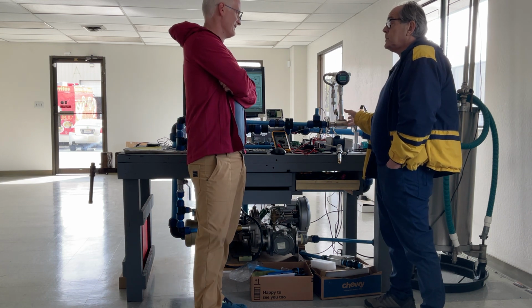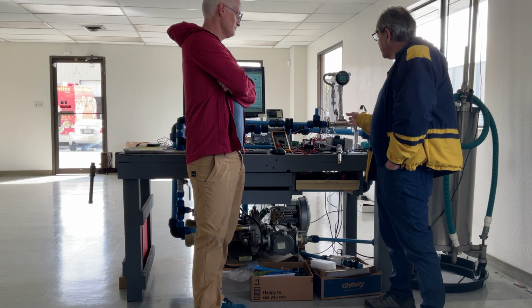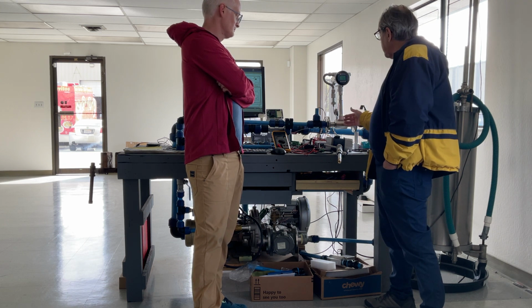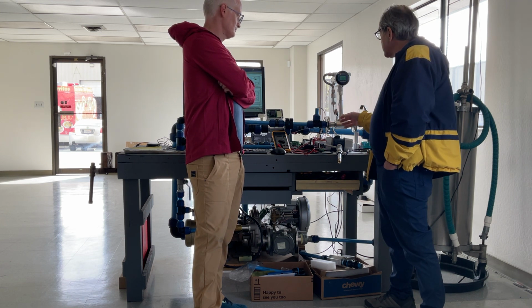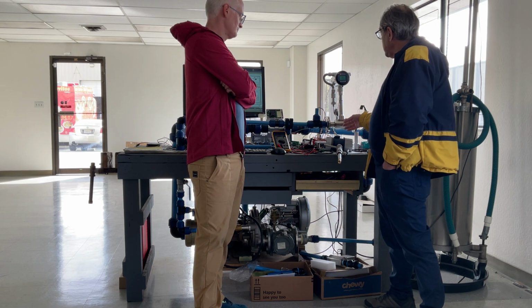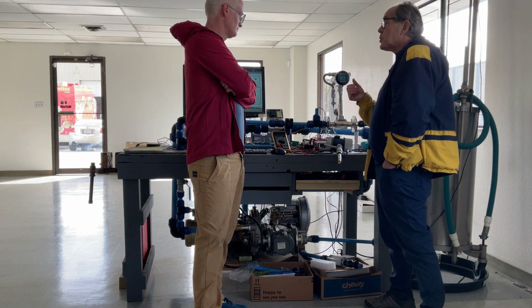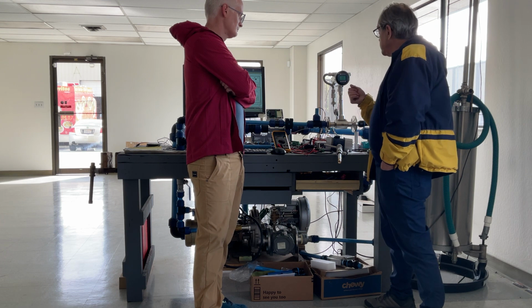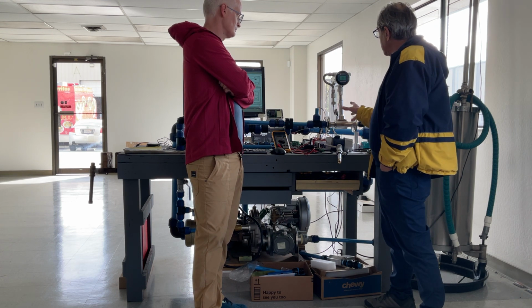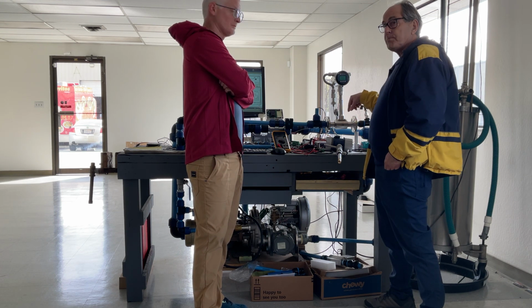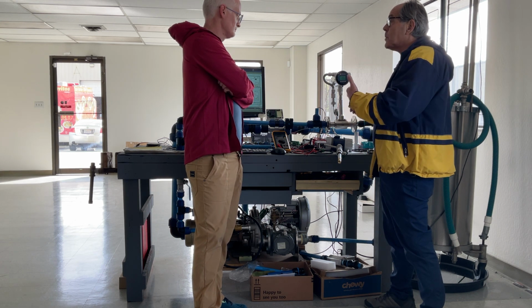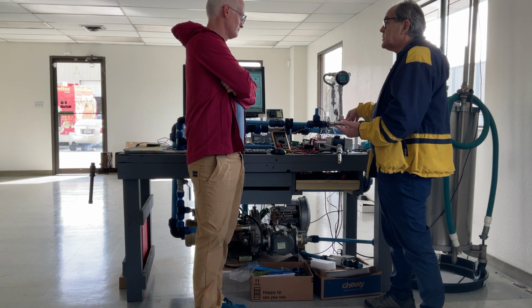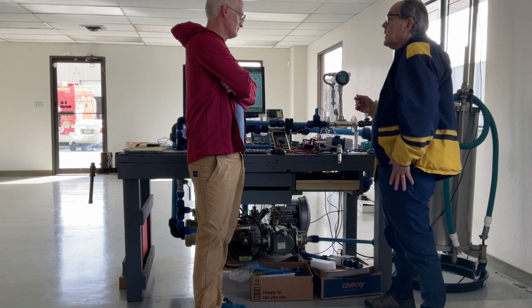Folks have done this with pressure. Some people have done it with density. Some people have done it in fluid mechanics using the change in the electromagnetic lines of flux. So you can actually make a vortex meter with a mag meter, electromagnetic sensors, and it has no sensitivity to vibration.